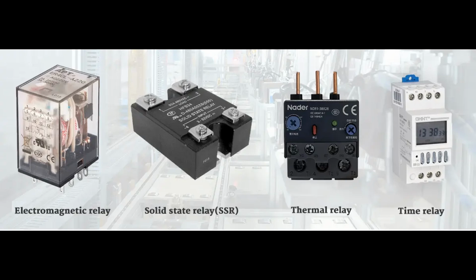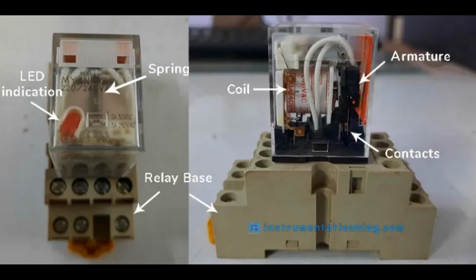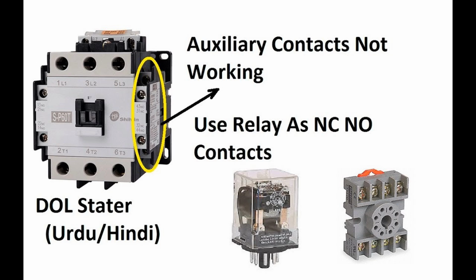Integration with motor starters. Self-heated thermal relays are commonly integrated into motor starters or contactors as part of a motor control circuit. They provide an additional layer of protection against overcurrent conditions, complementing the primary motor overload protection. Advantages. Self-heated thermal relays offer reliable and effective protection against overcurrent conditions, particularly in applications where motors are subjected to varying load conditions. They are relatively simple in design, robust, and cost-effective. Limitations. One limitation of self-heated thermal relays is their slower response time compared to electronic overload relays. They may also have limited adjustability and sensitivity, making them less suitable for applications requiring precise trip characteristics. Overall, self-heated thermal relays provide essential protection for motors and other electrical equipment, helping to prevent damage from overcurrent conditions and ensure the safe and reliable operation of industrial processes. These are just a few examples of thermal relays, and there are variations and combinations based on specific application requirements. Each type offers advantages and limitations depending on factors such as accuracy, response time, sensitivity, and environmental conditions.